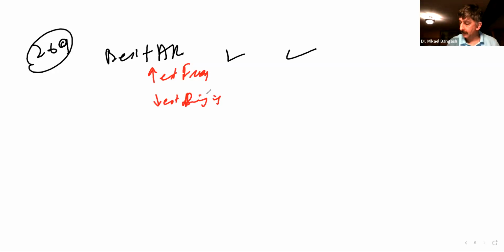Now, what remains is we have 4 examples. The one that we need to look for is which transducer has the lowest ringing, which is going to be the lowest number of cycles per pulse, and a higher frequency. Both of that will give us the best.